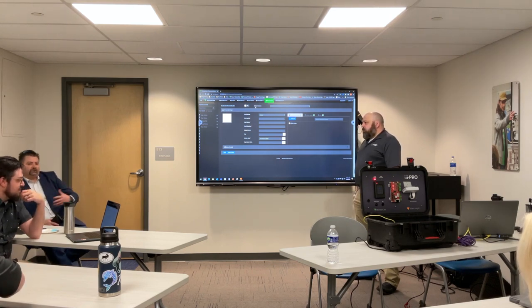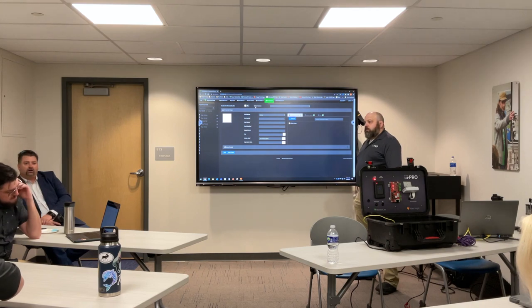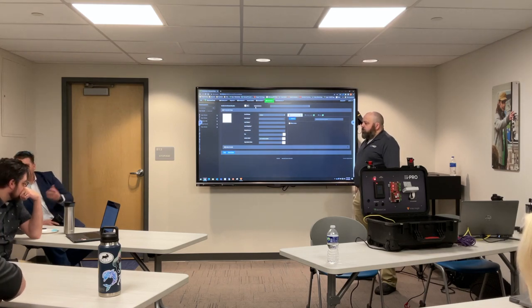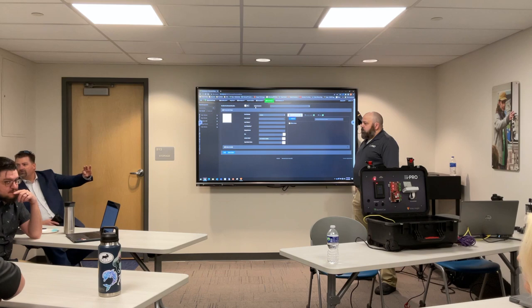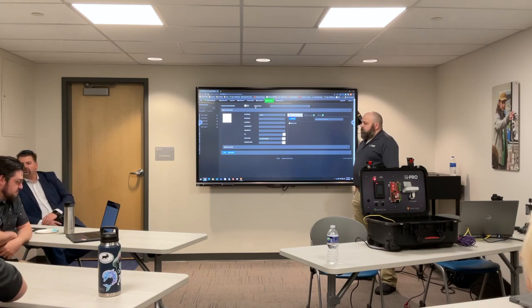But the best thing that we've come up with is integration with video. It gives you that extra layer. There are some locks out there, I'd say the most secure thing is a Maglock, but then it's power intensive, more expensive, and all that. And then you can get integrated locks with integrated door position switches in them. Kids look in the door jamb for the door sensor, right? And that's how they override it. Or if the lock is all integrated into one, they can push the thing in and override it that way. So there are some ways you can get around it. You can double up the door sensors in series.